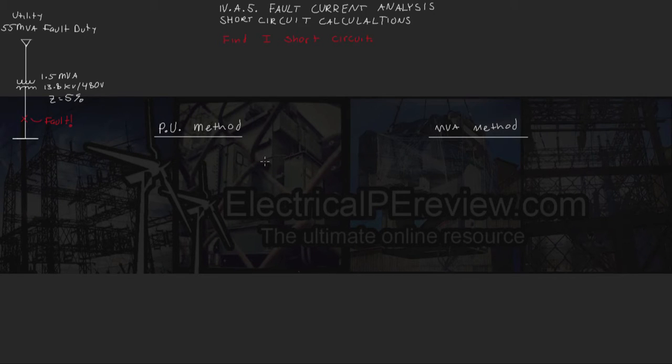We're going to solve it using two different methods, using the standard per unit method, and using something that we find a little more intuitive, the MVA method. So to start out we're given a utility, we assume infinite bus, and it has 55 MVA fault duty.